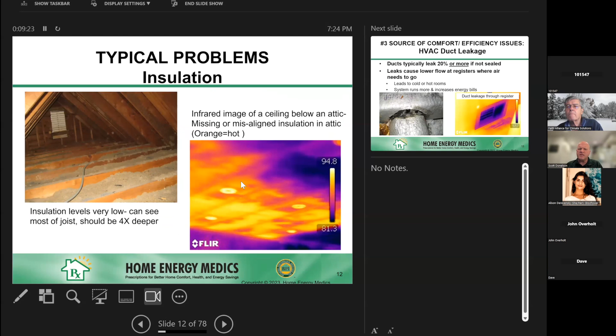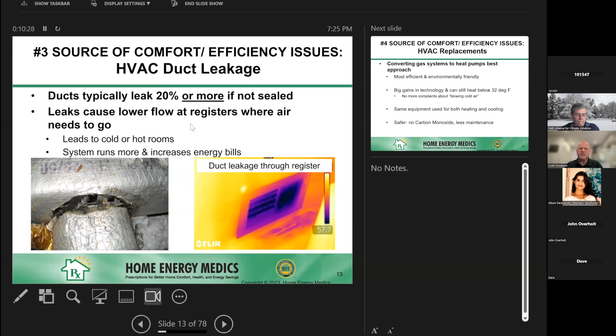Another big problem that's not really well thought about or understood is duct leakage. There can be disconnects in the duct. All the ducts are put together with what's called slips and drives, typically metal ductwork, and they all leak at the corners. What happens is the system's putting out all this air, but it's just leaking out along the way. I tell people it's analogous to a water hose where you turn on a spigot in the basement and pump water all the way up to the uppermost floor, and that hose is full of holes all the way up. Well, what you get out isn't what you put in, that's the kicker there. Sealing up the ducts makes a big difference, and it can all be done internally. You don't have to tear anything apart to do it. It's really pretty straightforward and easy.